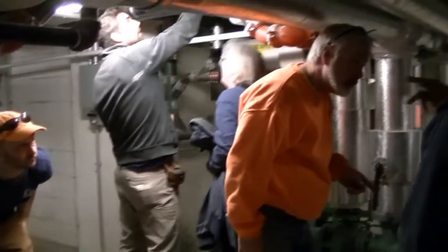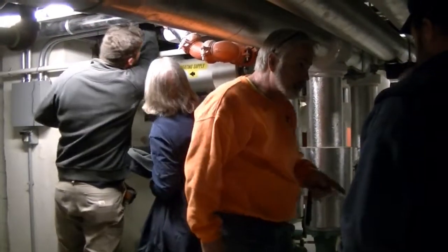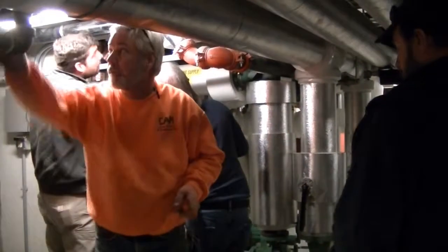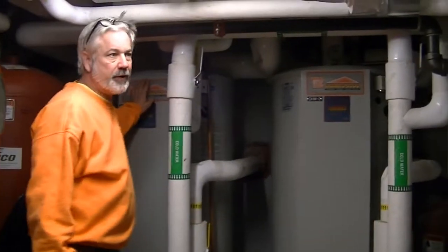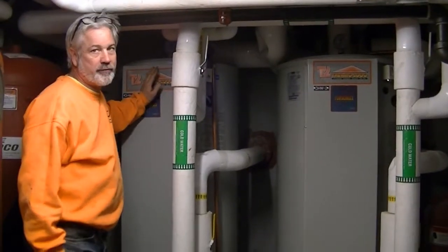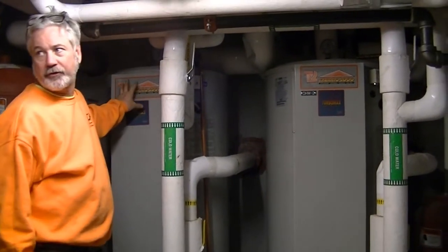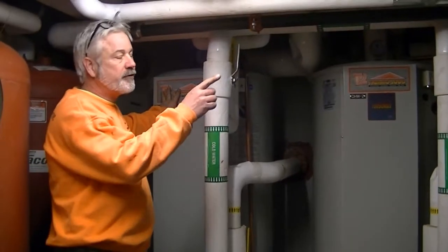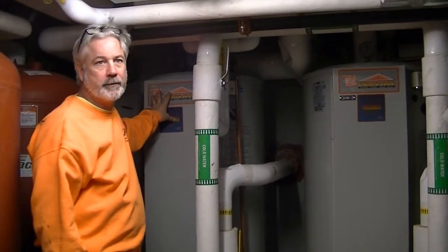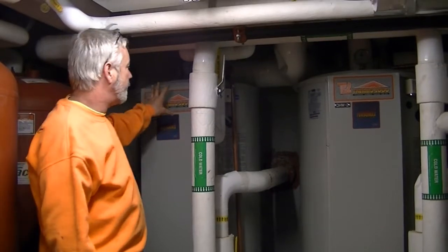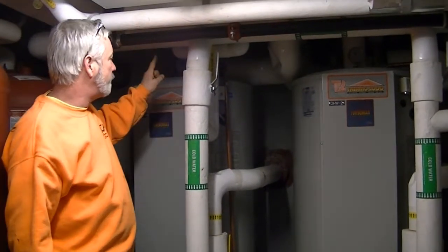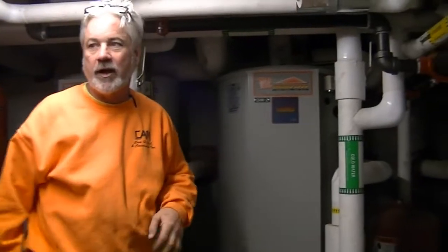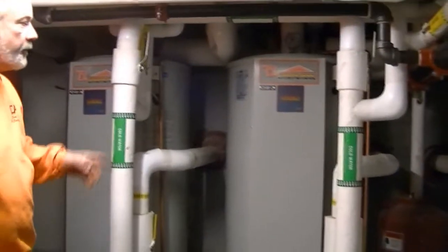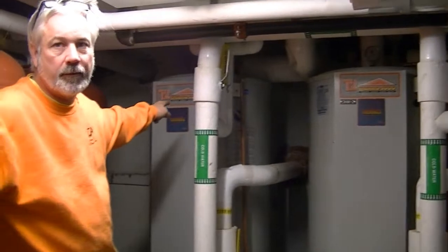Where's the water that goes into a well? Right there. Temperature sensor's right here. Yep. Okay? So if you come over to the sensor, the Viessmann system monitors the temperature in the 4 tanks. It's located on the first tank, okay? The other tanks do not have sensors in them. It's very important: if this tank goes down, you need to move the sensor from this tank to a tank that's still online, okay? It doesn't take an average, it only takes a single reading.